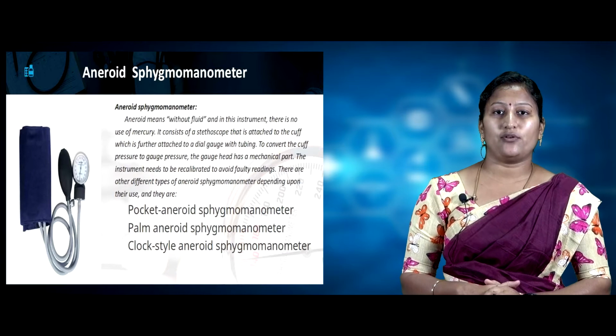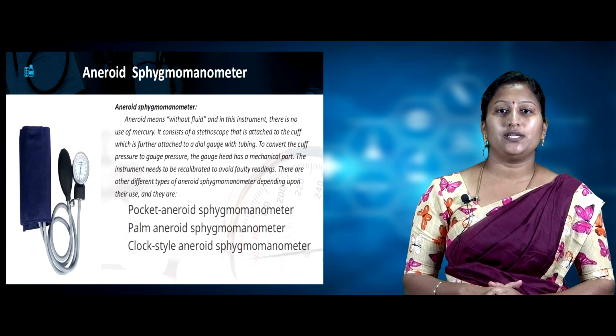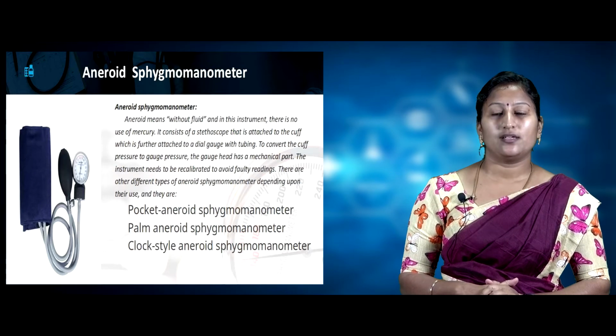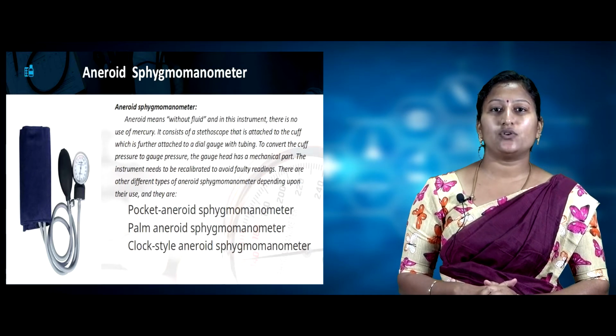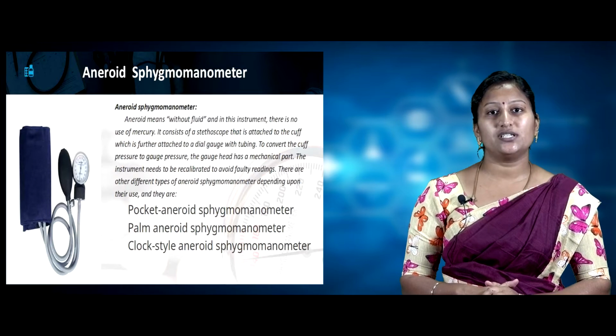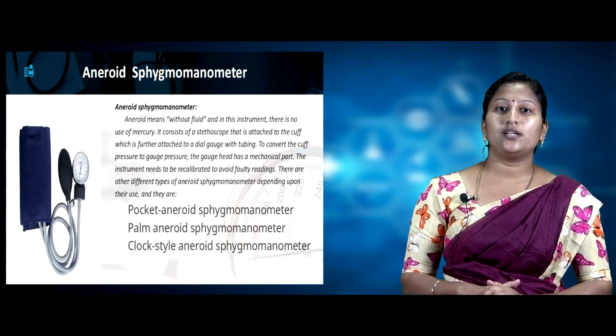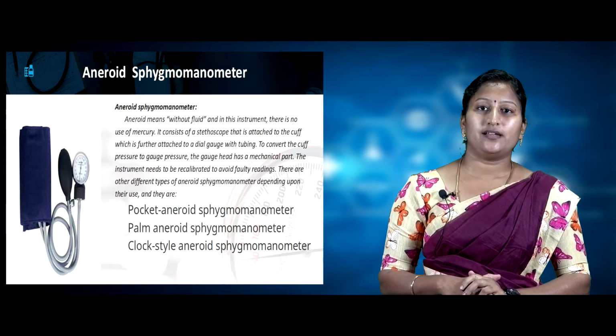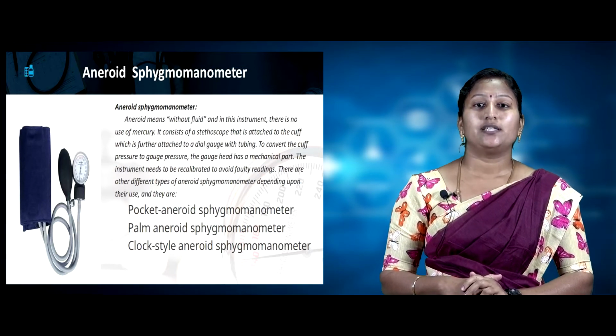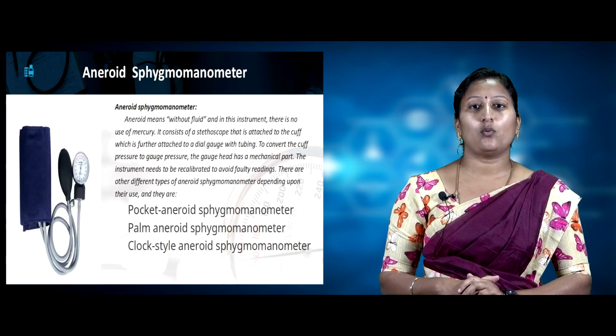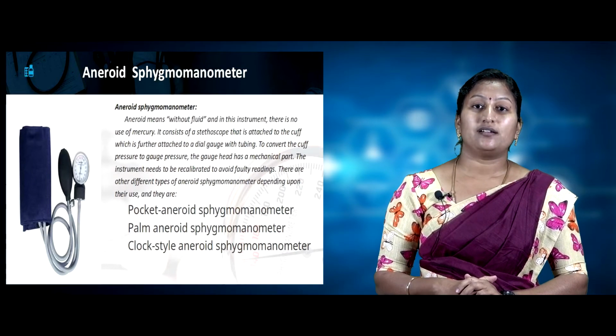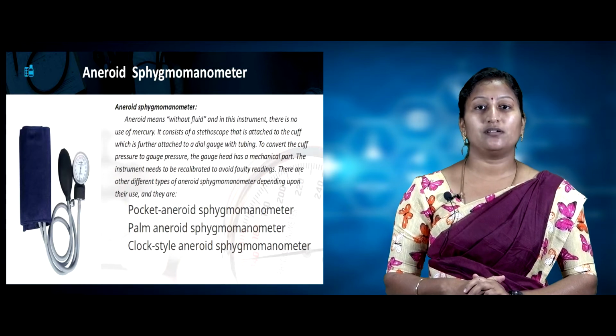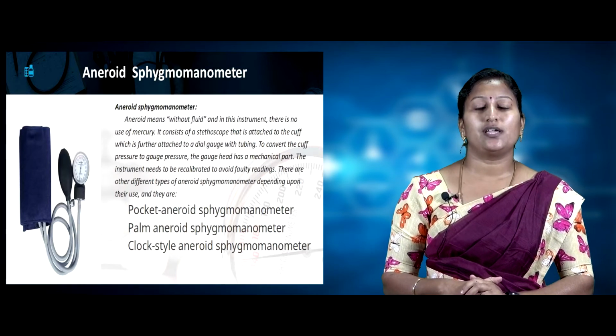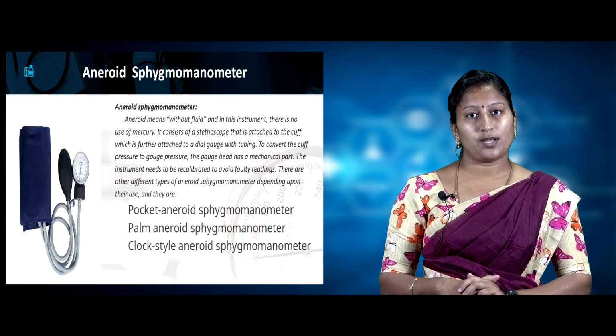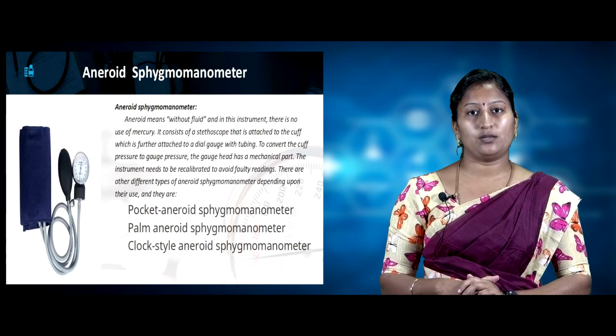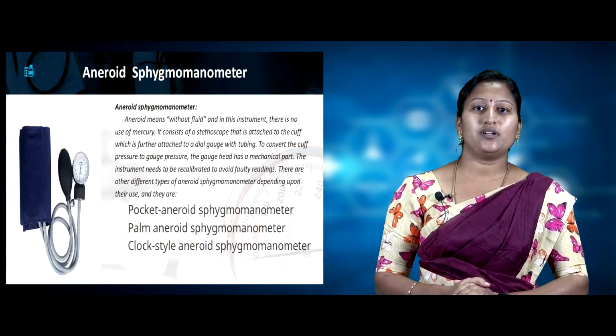Now let's see aneroid sphygmomanometer. The term aneroid means without fluid, and in this instrument there is no use of mercury. It consists of a stethoscope connected to a cuff, which in turn is connected to a dial gauge. To convert the cuff pressure into a dial pressure, the dial head has a mechanical part. The instrument has to be recalibrated to avoid faulty readings. There are different types of aneroid sphygmomanometer based on their different uses. They are pocket aneroid sphygmomanometer, palm aneroid sphygmomanometer, and clock style aneroid sphygmomanometer.